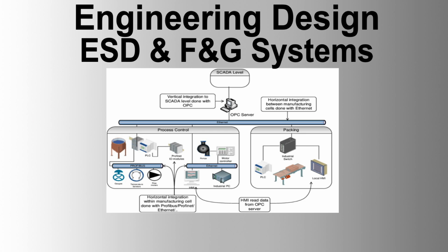Tile matrix display. 1. Display panel. Integrated ESD F&G common facilities matrix on the front panel. Hardwired tile matrix type with audible alarms, alarm accept reset, master key switches for overrides, local control via TFT interface, and hardwired shutdown push buttons.